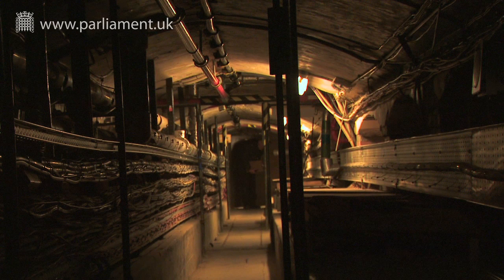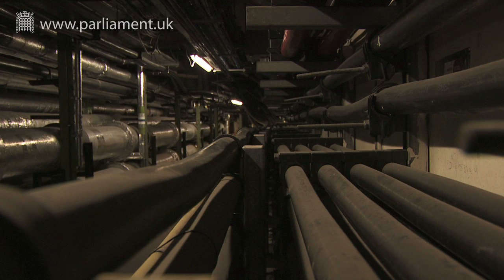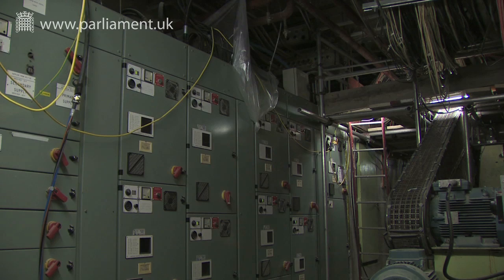The basement is thought to be the area at highest risk of fire, because of congested mechanical and electrical services, and the difficulty of access for the fire brigade. A sprinkler system is virtually impossible to install without first resolving the intensely overcrowded corridors. However, the current programme will deliver a high-pressure water mist system in smaller pipes, pumps, and water supplies to the basement and high-risk areas.